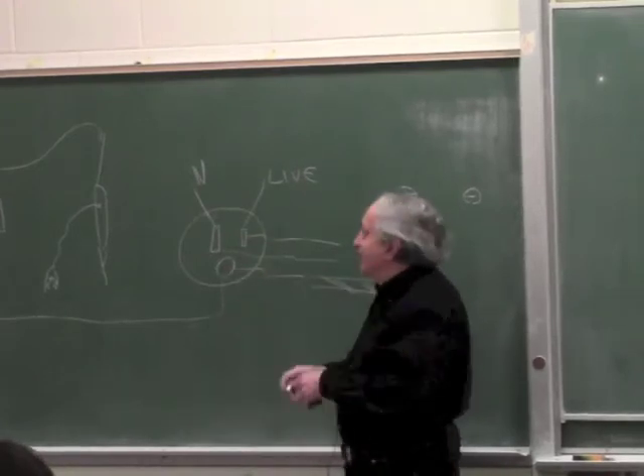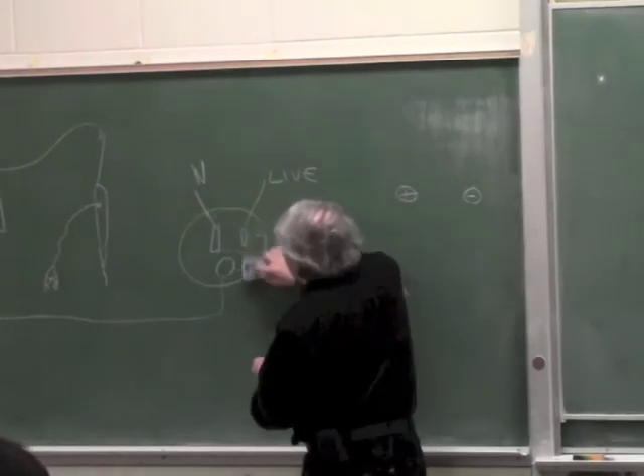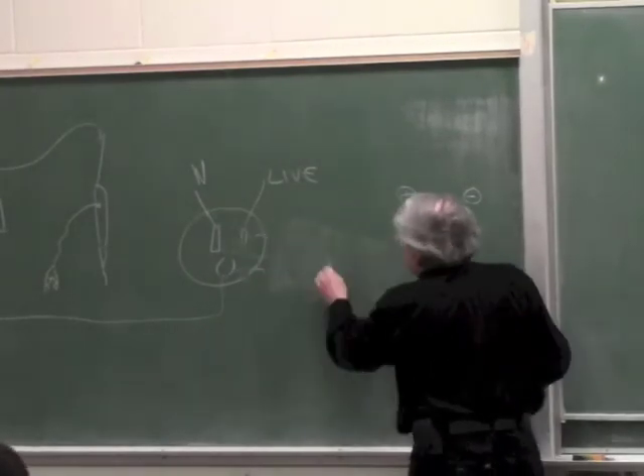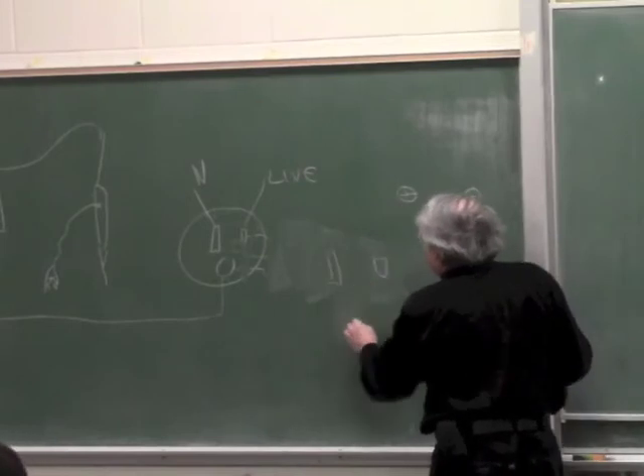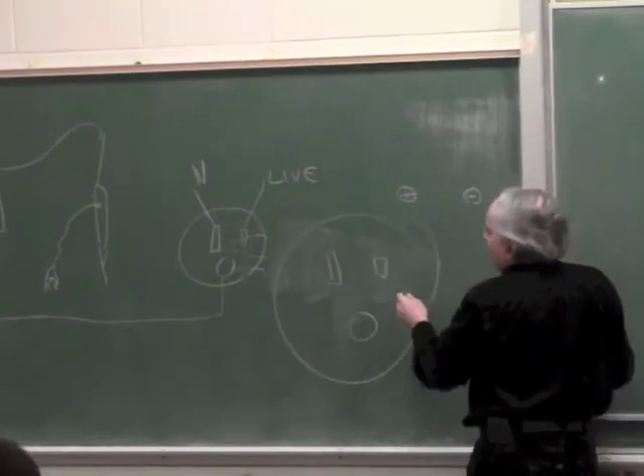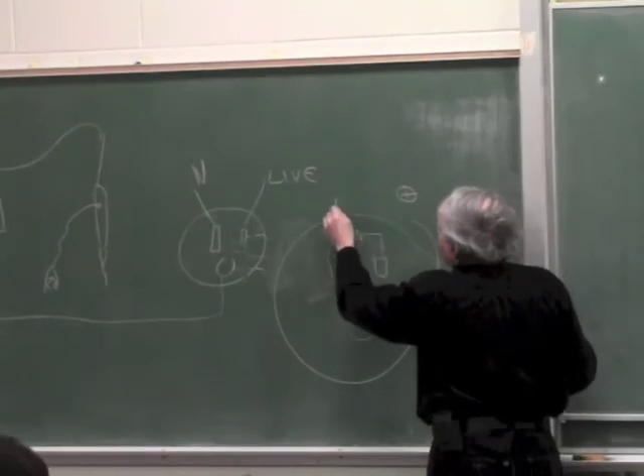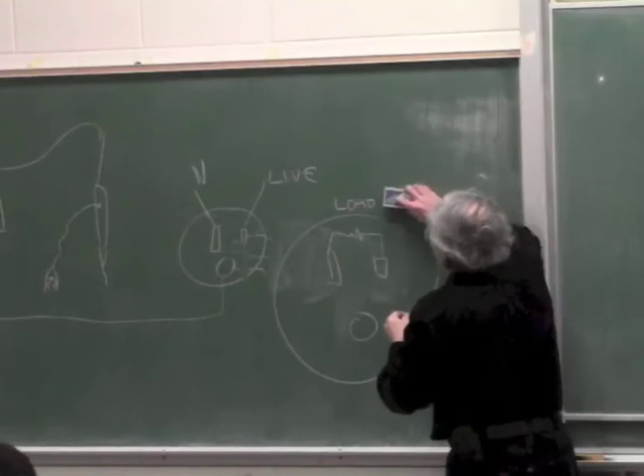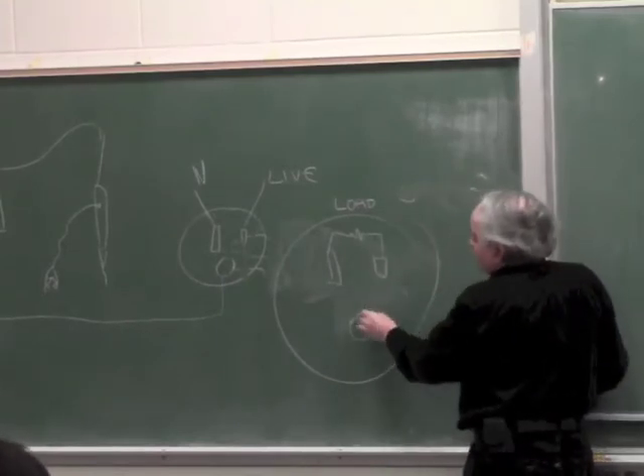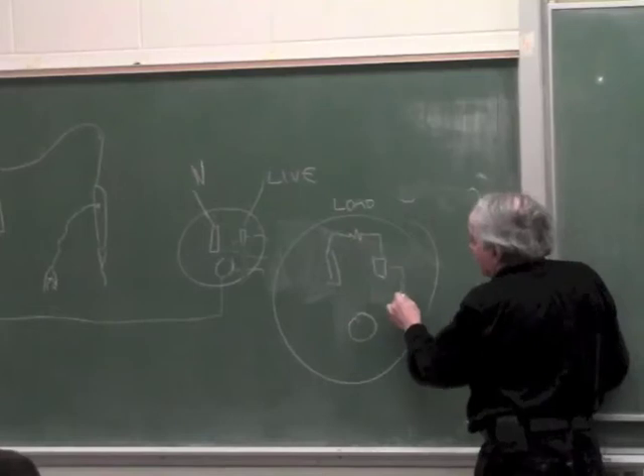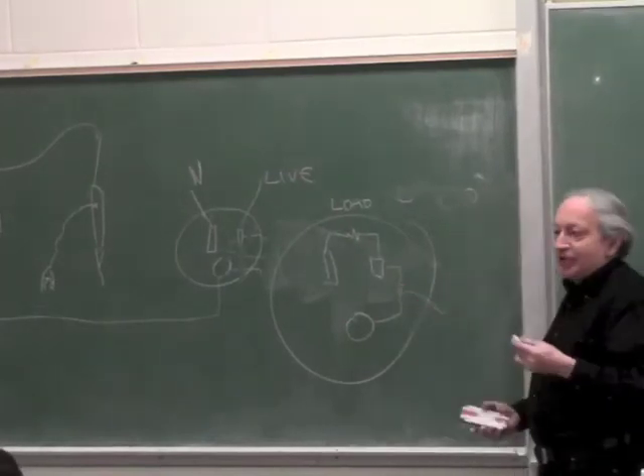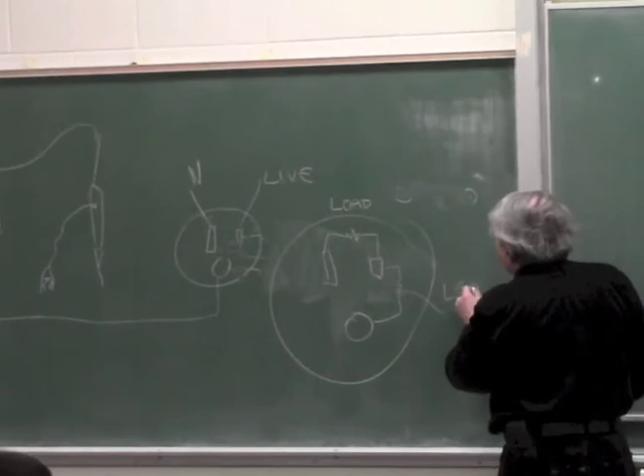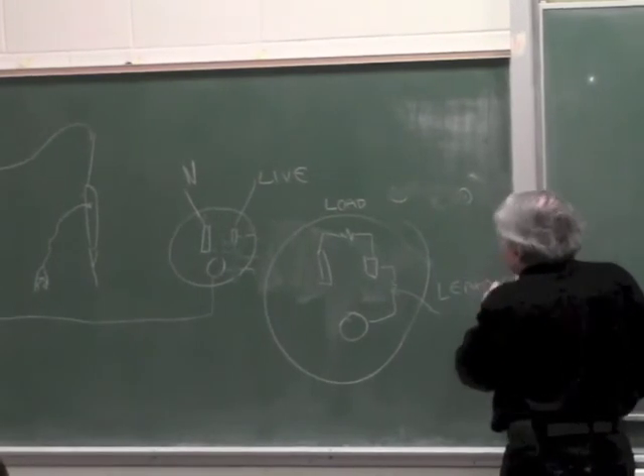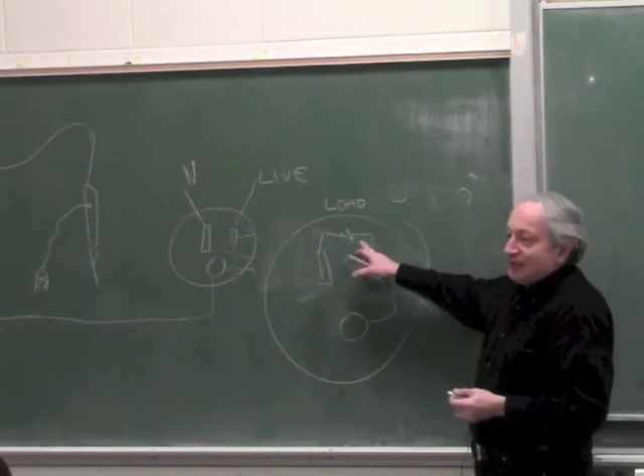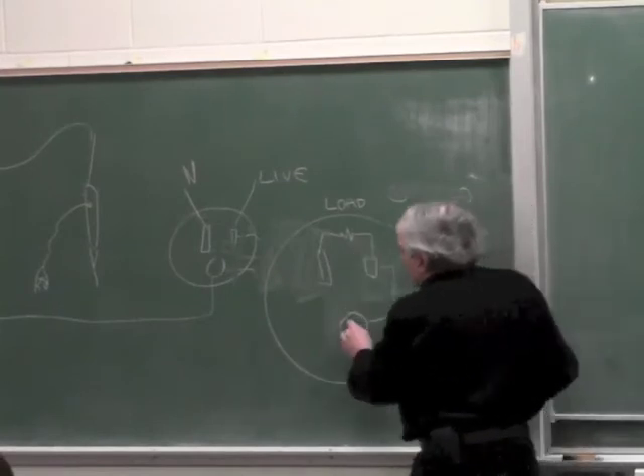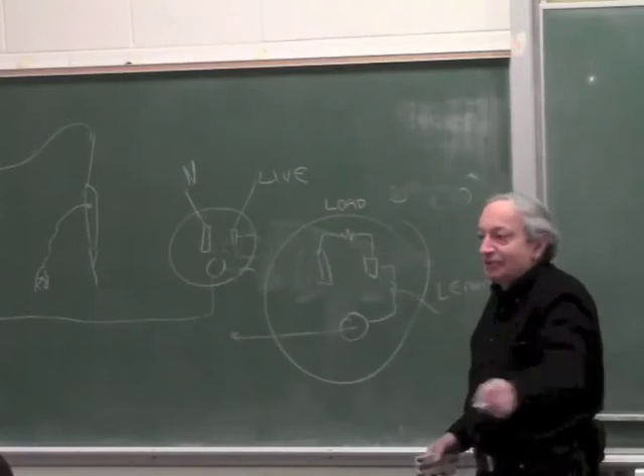But in reality there are leakage currents, so I want to remind you again that in reality, if this is your outlet, this is a normal load. The idea was that if this touches this, it will blow the breaker, but in reality there is a leakage current because of imperfect insulation, and because of this leakage current, which could be quite big, it's not going to blow the breaker, right? So because of this leakage current, there are actually currents flowing in a house over the ground wires.